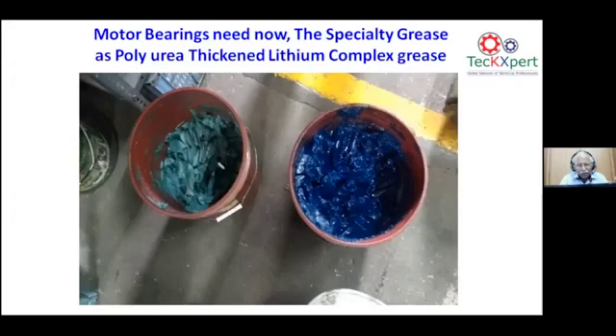Coming to the motor, one is voltage imbalance and current imbalance. See, if voltage imbalance is 4%, current imbalance is almost 40%. Now, lubrication: we have gone for multi-purpose greasing because it costs 150 rupees per kg. Maybe the specialty grease is going to cost around 600 or 800 rupees, but still, polyurea thickened lithium complex grease has better shear resistance. At the same time, its life is more. The mean time between greasing can even be doubled.